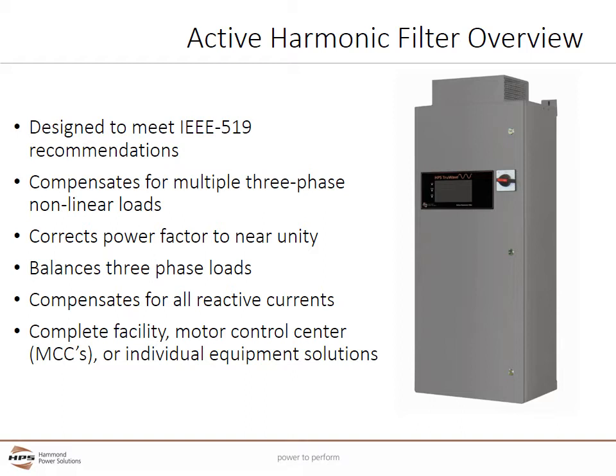Single-phase nonlinear loads, like computers, DC power supplies, and small chargers, must be mitigated with other devices like harmonic mitigating transformers. Active harmonic filters can also correct power factor to unity and balance three-phase system currents. In addition, active harmonic filters compensate for all reactive currents and offer complete facility, motor control center, or individual equipment solutions.